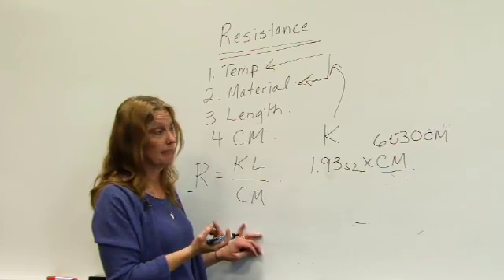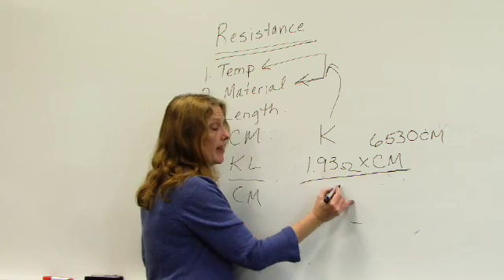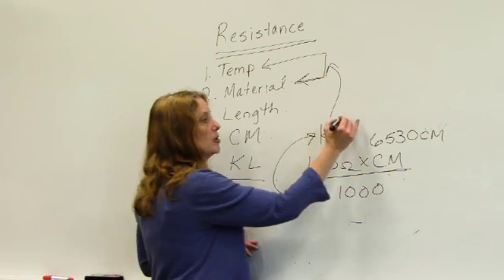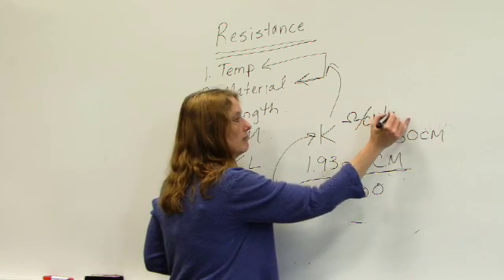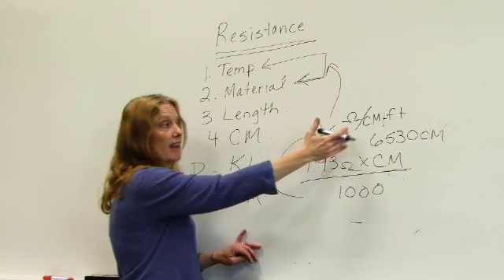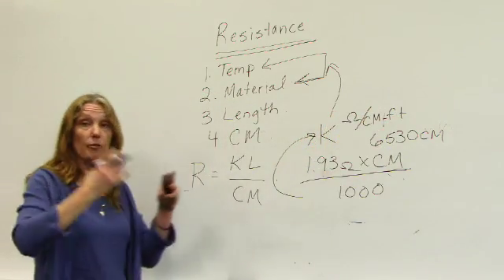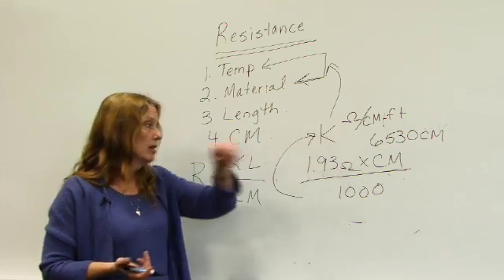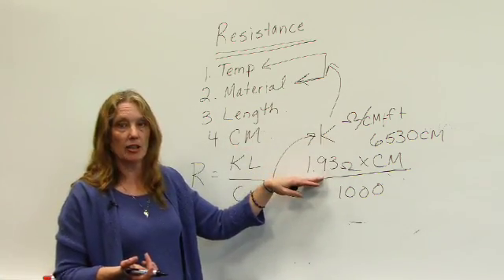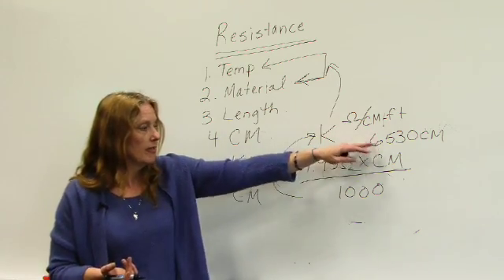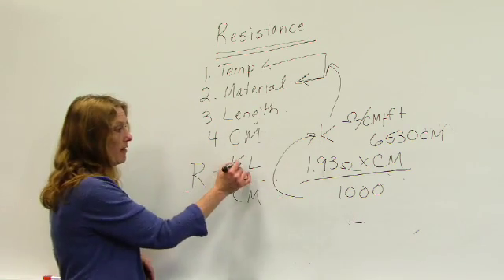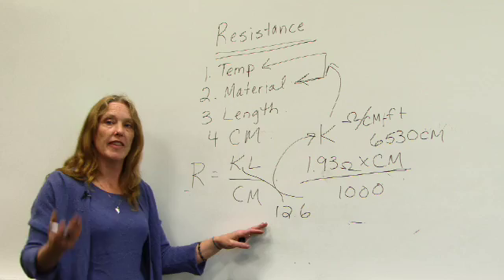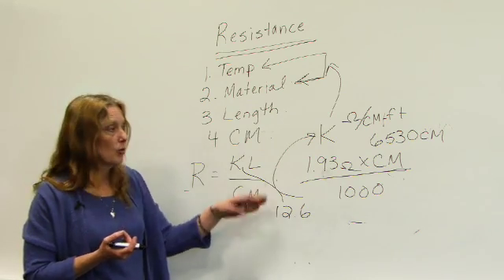A lot smaller than our 62,500 one. I take this times this, divide it by a thousand, and that is going to give me K. K is basically measured in ohms per circular mil foot. What that means is I have a wire one foot long with one circular mil. So by taking this number 12 gauge copper conductor at the code book value of taking 1.93 times 6530 divided by a thousand, I would then come up with a K value or constant of 12.6. Now you'll often find out there a 10.4. That is based on a lower ambient temperature, which would then bring these values down.